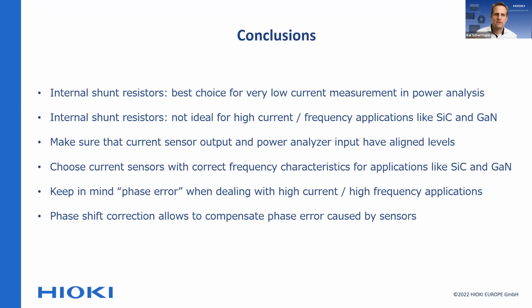One of the things that is important is you should make sure that your current sensor output and your power analyzer input have aligned levels. So even if you use current sensors and power analyzers not from Hioki, which is absolutely fine, you need to make sure that the sensor you pick is matching the ADC input and the shunt value of your power analyzer. These things have to match. You can have the best power analyzer, which boasts a super great accuracy. If at the end of the day, the signal that you put in from your current sensor is super low, your signal to noise ratio is far too low, and you need to have a high signal to noise ratio and not a very low one. So from that point of view, that is really something to look at.